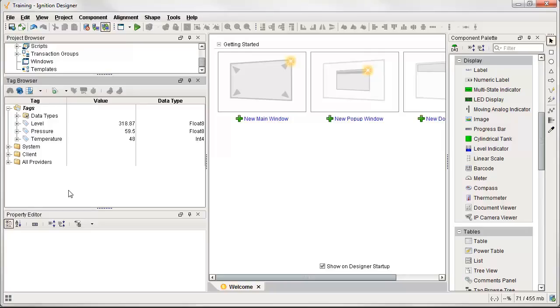Let's create another driven scan class here, but this time let's investigate the one-shot option. That feature allows us to poll tags manually when we want to. So rather than polling at some rate, depending on the condition, we're going to use the condition, and on the rising edge of that condition, we're going to poll the values once, and then wait for that condition to go back to being false, and then back to true for it to poll again. So it's a way of only polling it manually when we want to.